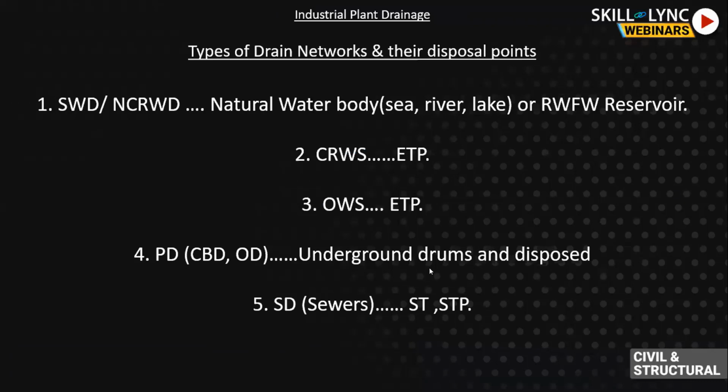You should do all free flowing systems or gravity drains. They are the cheapest to design. Introduction of pumps certainly increases the cost. If throughout the round the clock, 24/7, pumps are pushing the drainage into the disposal points, it is certainly a costly design. So be watchful. We are answerable to whatever we design. There is certainly a check or audit happening. So the question will be why you designed a pumped system. The safest and cheapest is to design free flowing.